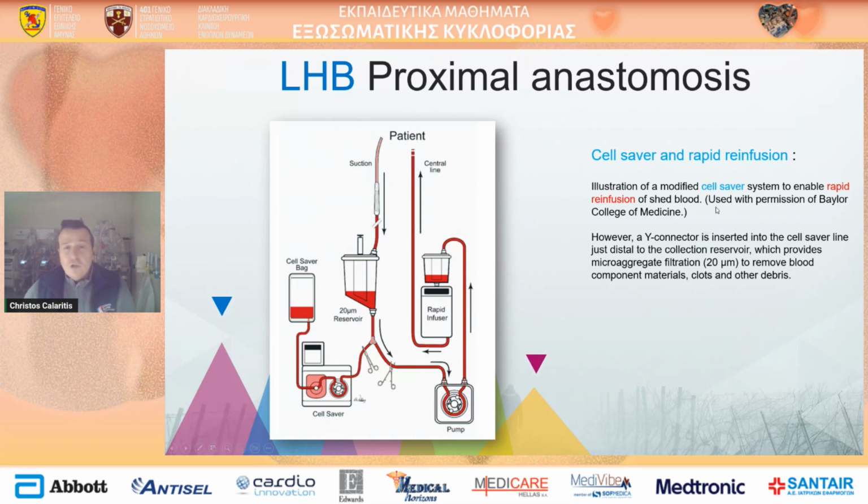So this is an illustration of a modified cell saver system to enable rapid reinfusion of shed blood. There's a Y connector that is inserted into the cell saver line just distal to the collection reservoir, which provides microaggregate filtration to remove blood component materials, clots, and other debris.